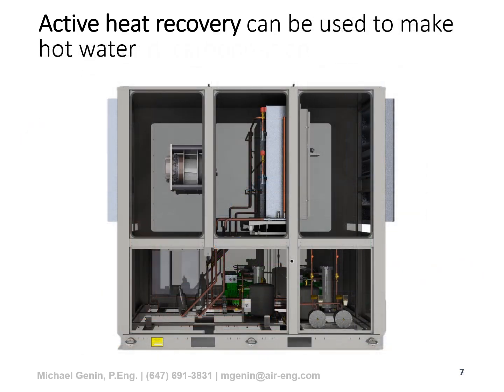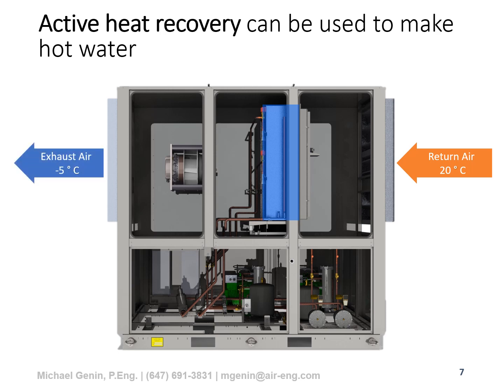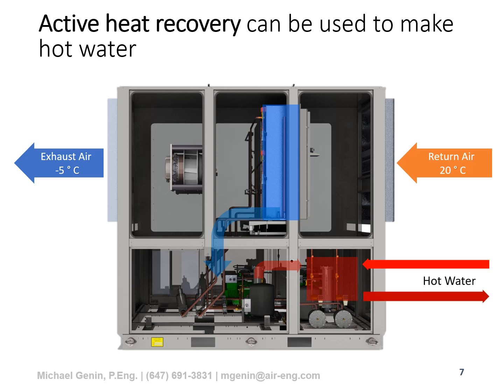Active heat recovery can also be used in a form in which hot water is generated from this waste exhaust airstream. In a similar fashion, the return air is going to be brought over the refrigeration system, where it will cool that exhaust air again to a very low temperature to extract as much heat as possible. The compressor is going to dump this heat this time not in an airstream but into a water-cooled condenser where hot water can be produced.